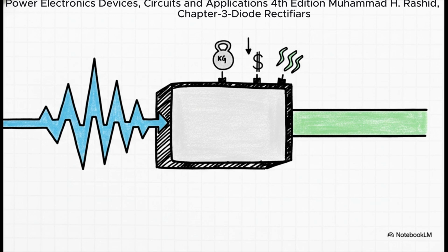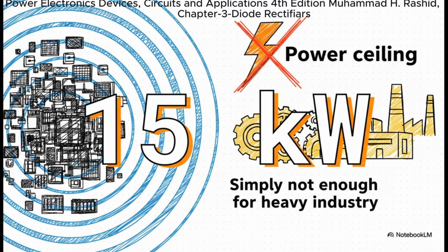And it's a huge problem. It creates what we call dirty power, it's unstable. To clean it up, to make it usable for sensitive electronics or big motors, you have to add filters. But here's the catch: because that voltage dips all the way to zero, the filters you need have to be huge, heavy, super expensive, and pretty inefficient. All of this, the ripple and the giant filters needed to deal with it, creates a very real practical power ceiling. For most applications, a single-phase rectifier just isn't going to cut it above about 15 kilowatts, and for heavy industry, that's nowhere near enough power.